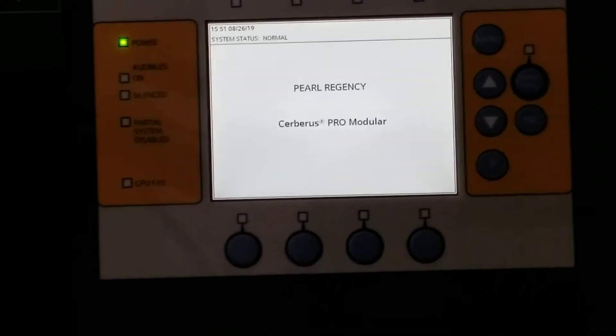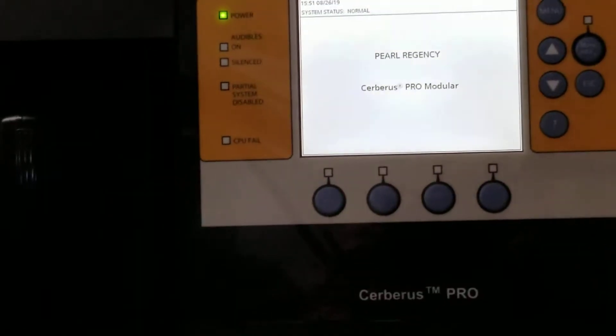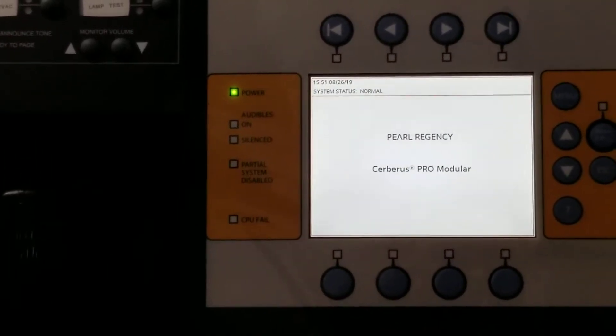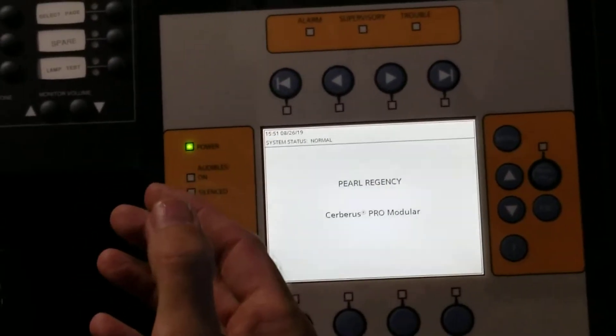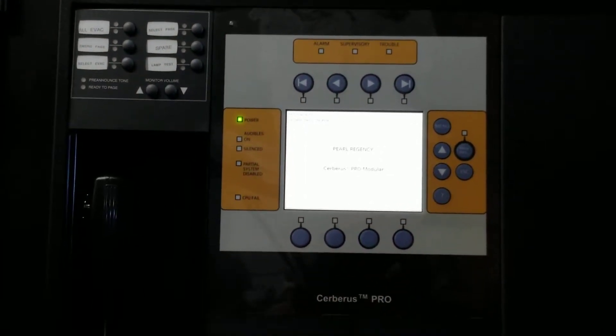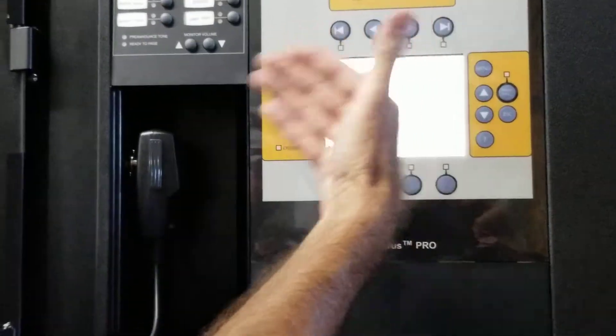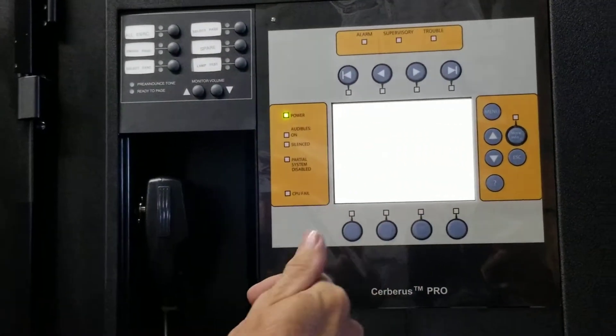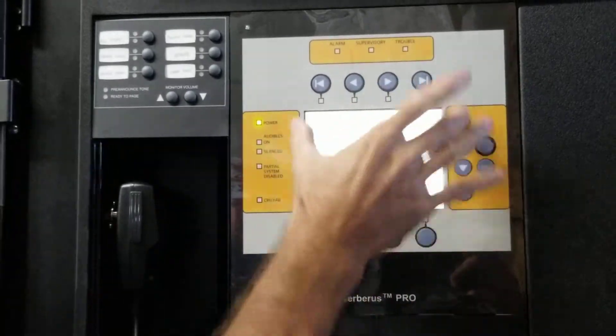I just want to show you one thing that has gotten me before. So if it's in trouble and then an alarm comes in, the alarm pops up and you hit acknowledge silence, but you can't reset it. It's because you have a trouble you haven't acknowledged. Alarms always take precedence over a trouble. So if you don't hit acknowledge for the trouble, it won't reset, but the fire alarm will stay up in the panel.